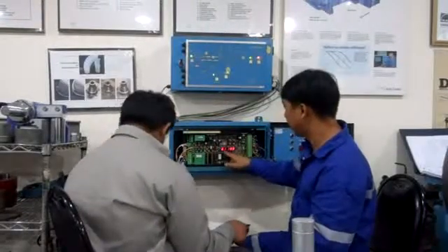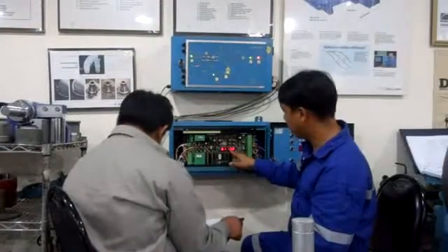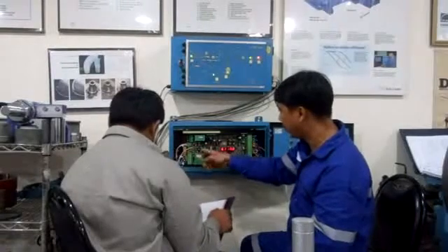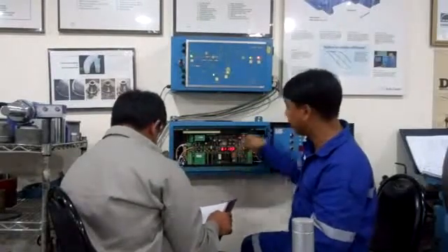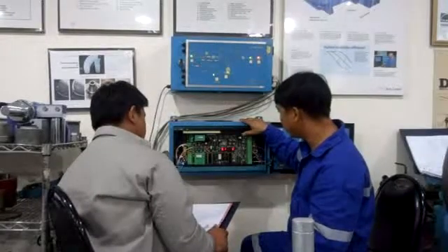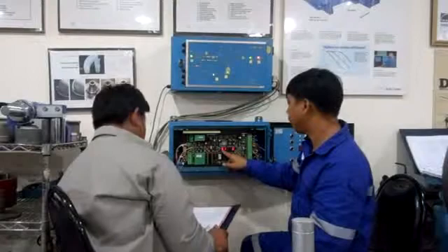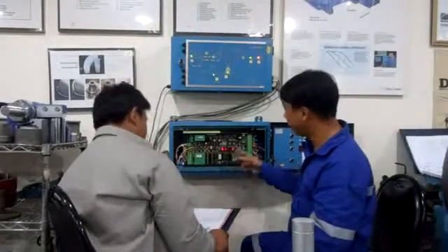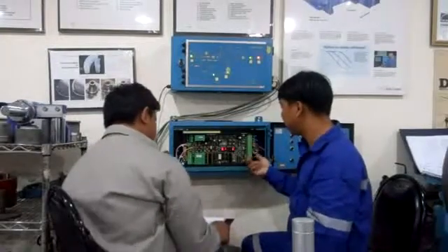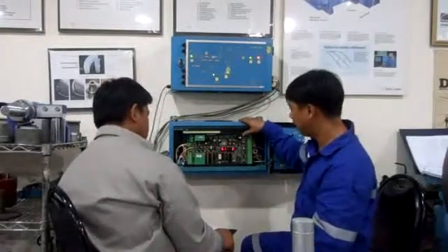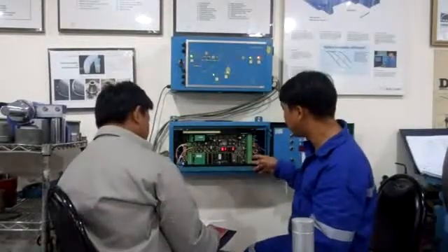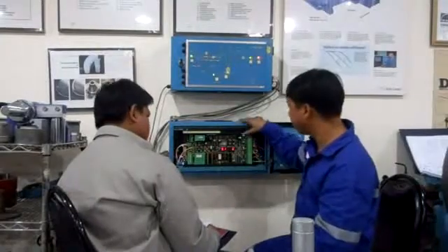Okay. 8.1 is about the fuses. Okay. So you will see if you were going to remove, if you have the flow switch, then it will indicate it there. Okay. We have the value. Next. 9.1, that's indicated E. But if you want to do it, you have to jump here. Okay, we have to jump here, but it's not necessary. That's indicated E is fault, but if you have to do the testing, we have to do the jumper.